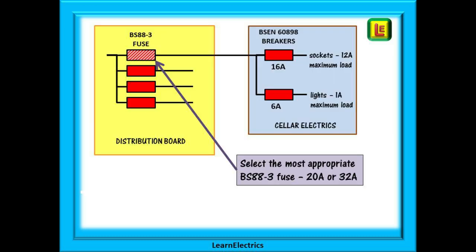For this scenario we have a distribution board populated with BS88-3 fuses. A circuit is to be taken from one of the fuses into the cellar where a small consumer unit is installed with just two MCBs. A 16 amp breaker for the socket and a 6 amp one for the lights. There will only be two sockets on this circuit and the attached equipment draws less than 12 amps in total. The lighting circuit feeds two luminaires drawing less than one amp.